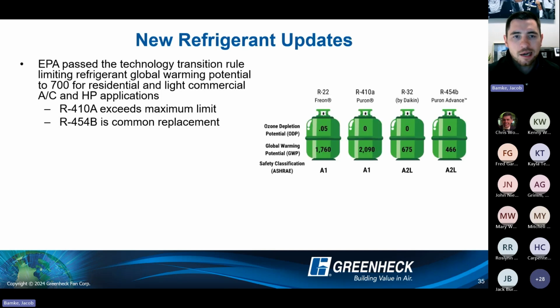But the updates, really to get into some more detail, the EPA passed what they're calling the technology transition rule. And this is limiting your refrigerant global warming potential to 700 at most for all residential and light commercial air conditioning and heat pump applications. You look at the table on, or the graphic on the right, our 410A that we use today has over a 2000 GWP value. So well exceeding the threshold of that 700 set by that technology transition rule.